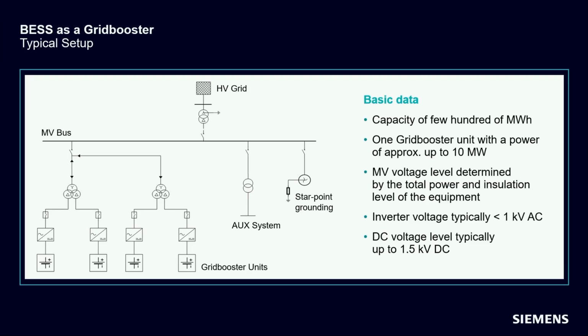The required operation time is one of the biggest differences between the grid booster and a conventional BESS application. The grid booster is expected to provide a large amount of power over a relatively short time frame, for example for a few seconds, up to 1 hour, while other BESS applications may provide smaller amounts of power over a longer time frame.